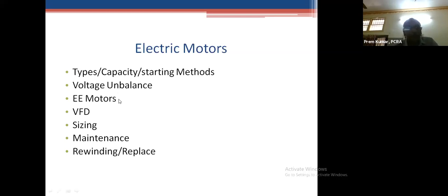Again, do not oversize the motors. For example, in a compressor, I saw they used IE4 motors, super energy efficient motors, but they were given a service factor of 25%. The purpose itself is defeated. So when you are considering VFD motors, check with the manufacturer whether it's suitable for inverter duty motors. Sizing is very important.